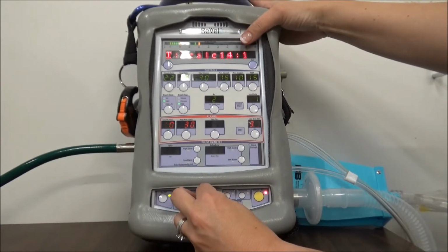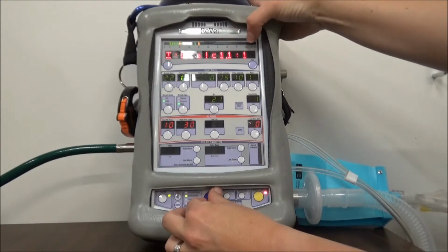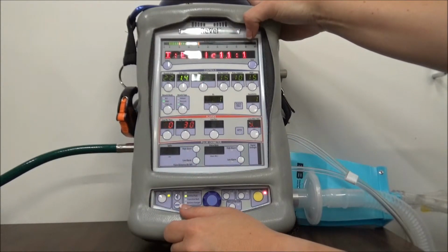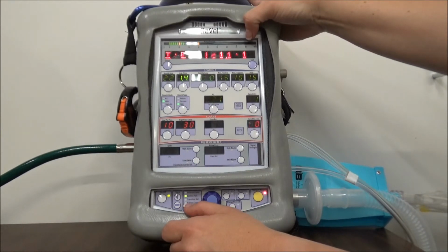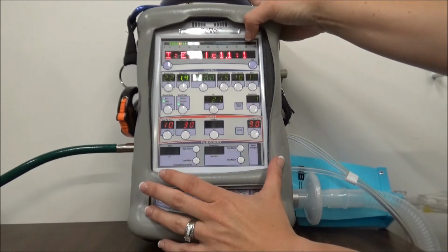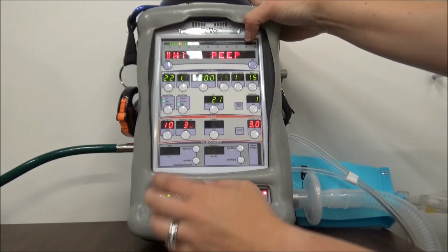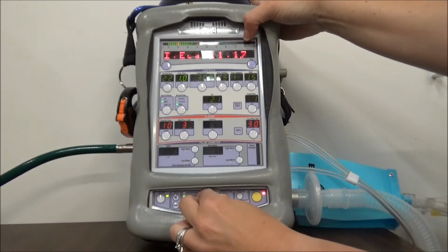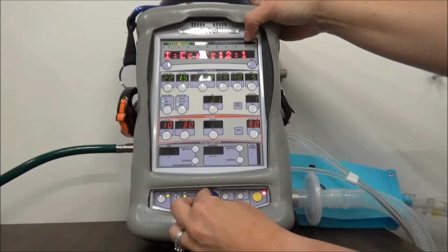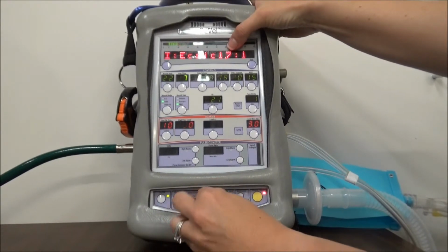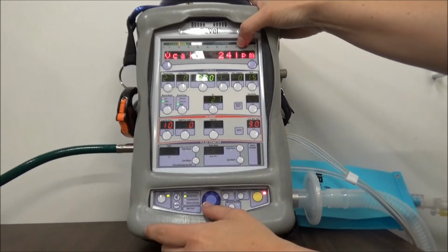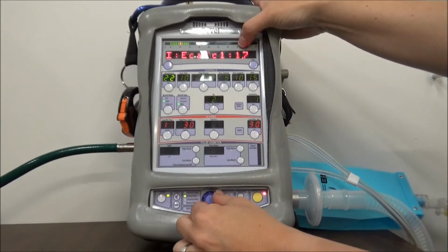So right now we're at a 1 to 1, a 1.4 inspiratory time. That means you're in equal time inspiratory phase as you are the expiratory phase. Now where we talk about really good oxygenation is when you completely inverse that, so you're in a 2 to 1 I/E ratio. So let's see what that looks like. I'm looking up here, I'm titrating my inspiratory time till I get to a 2 to 1, and it's going to limit me because it can't do that with the tidal volume and the respiratory rate.